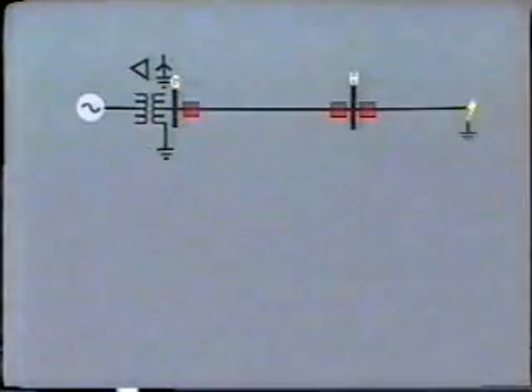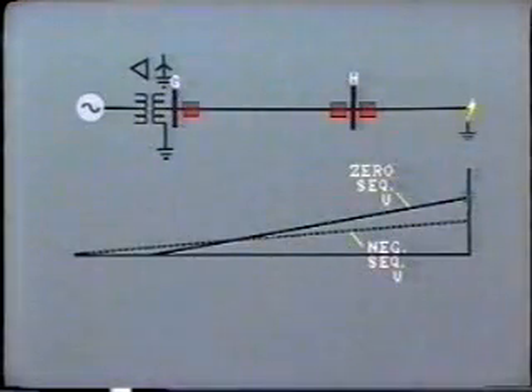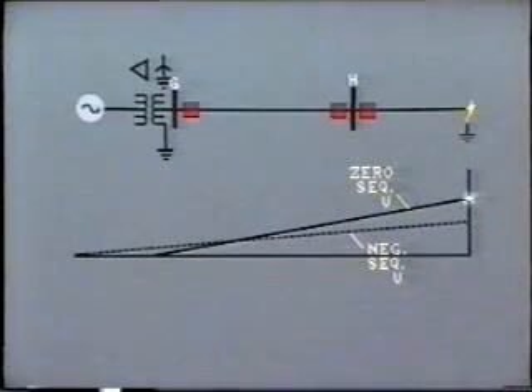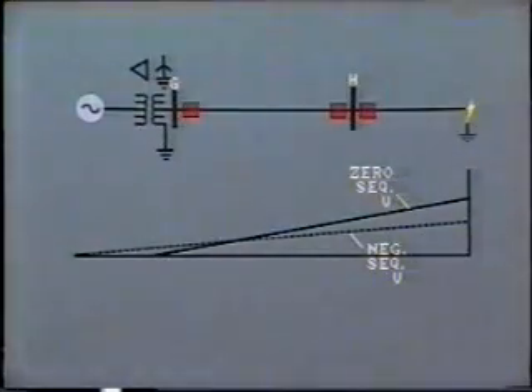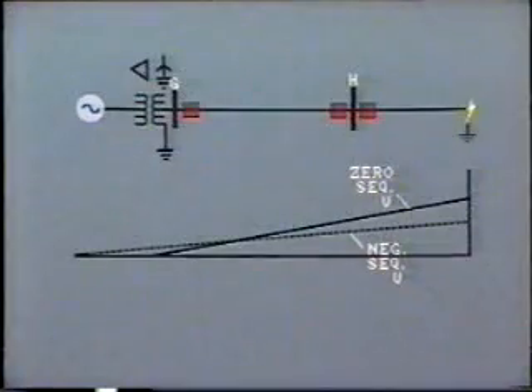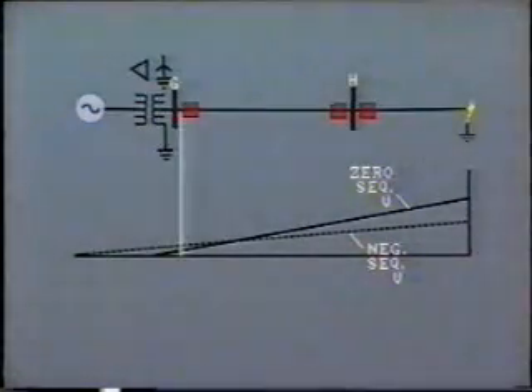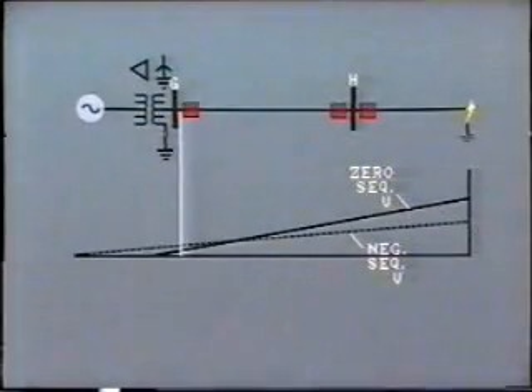Why is this? Well, when a ground fault occurs, the zero sequence voltage is maximum at the fault, but is close to 0 at the supply transformer, the neutral of which is solidly grounded. This diagram shows the voltage profile. Remember that the relay is located here at the beginning of the line on bus G.